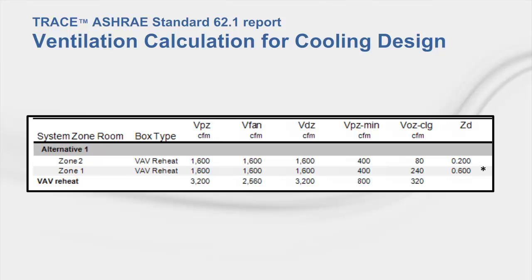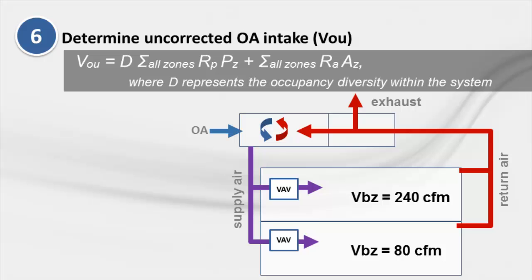In the TRACE report for ventilation calculations for cooling design, TRACE identifies Z sub D for each zone and denotes the critical zone with an asterisk on the right side of the report. In Step 6, we determine the uncorrected outdoor air intake air flow, V sub OU, for the system by totaling the breathing zone outdoor air flow requirements from all spaces served by a common system using equation 6-6.